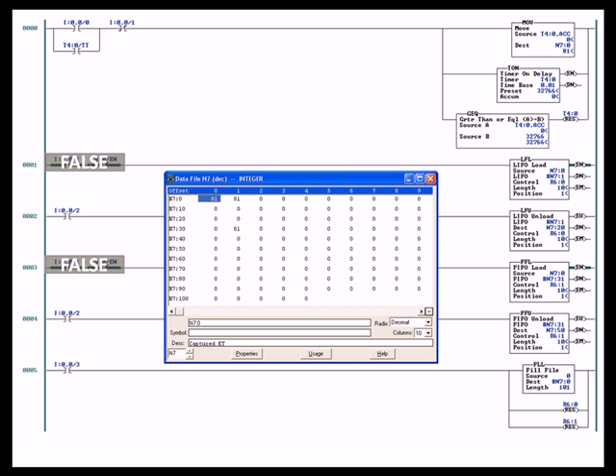You have a free running timer, meaning that T4:0 timer data type being instructed by a timer on delay instruction is accumulating continuously as long as the rung is true. The move instruction is doing a word copy, copying the 16-bit integer from T4:0 accumulate register into N7:0 every single program scan.